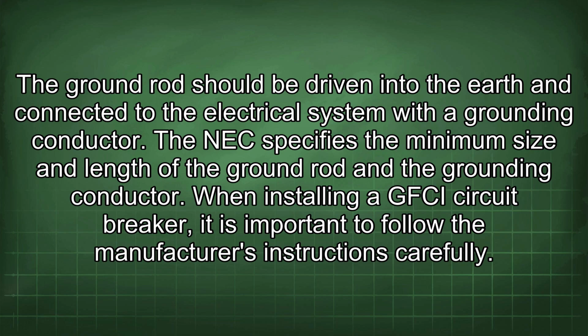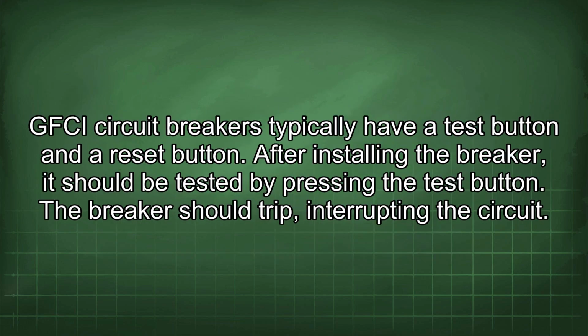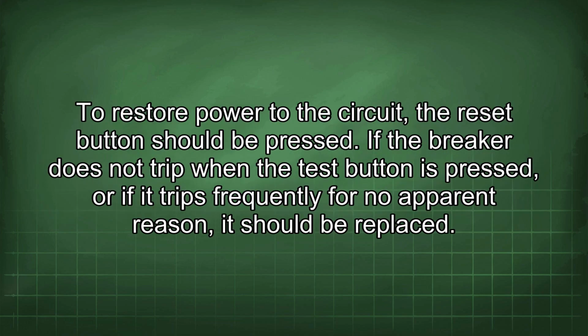When installing a GFCI circuit breaker, it is important to follow the manufacturer's instructions carefully. GFCI circuit breakers typically have a test button and a reset button. After installing the breaker, it should be tested by pressing the test button. The breaker should trip, interrupting the circuit. To restore power to the circuit, the reset button should be pressed. If the breaker does not trip when the test button is pressed, or if it trips frequently for no apparent reason, it should be replaced.